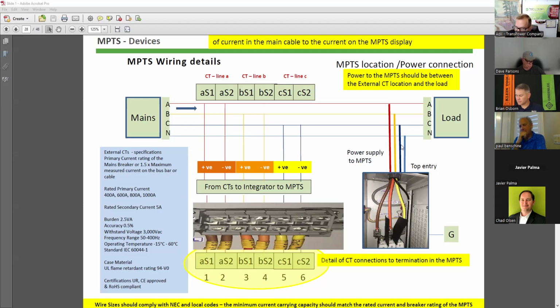You need a disconnect switch or a breaker in your switchgear to completely turn power off to the MPTS according to code. In many places, they have simply tapped power and connected it like I've shown here, with no disconnect switch. That is not the right way to do it.